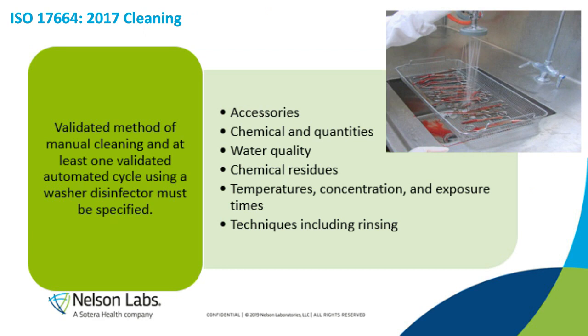When we look at ISO 17664-2017, it gives very specific information regarding a validated method of manual cleaning, and it requires at least 1 validated automated cycle using a washer disinfector. It also includes adding information such as accessories, the chemical and the quantities of the chemicals that are used, the specific water quality of each step, any chemical residues that need to be tested. It also requires the specifications of temperature, concentration, and exposure times, and all techniques, including all the rinsing techniques.